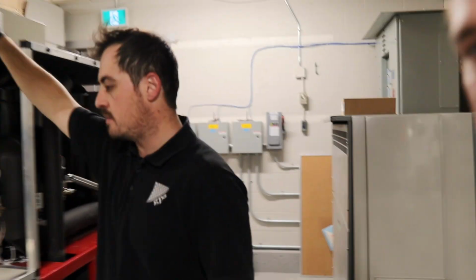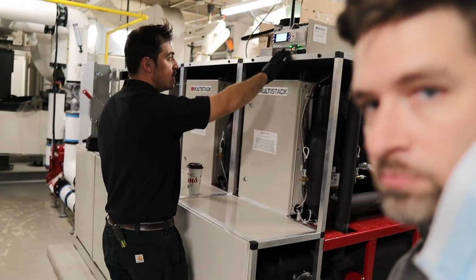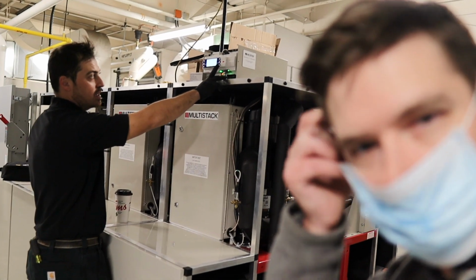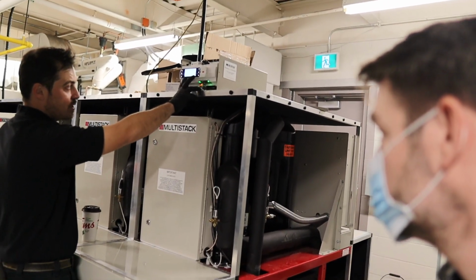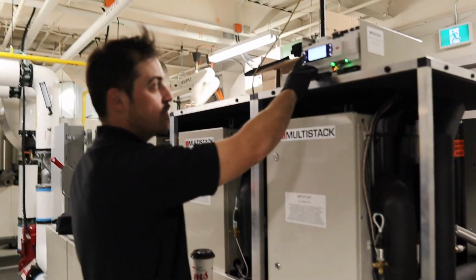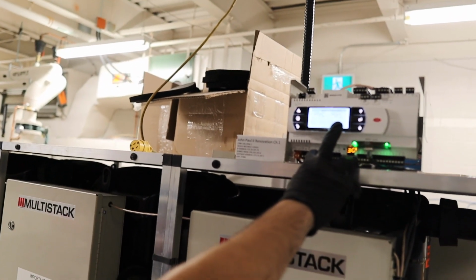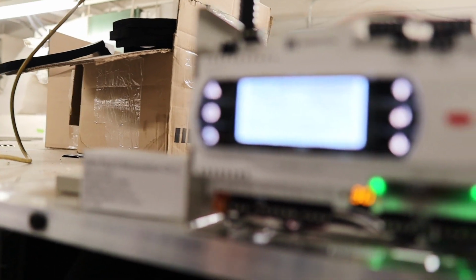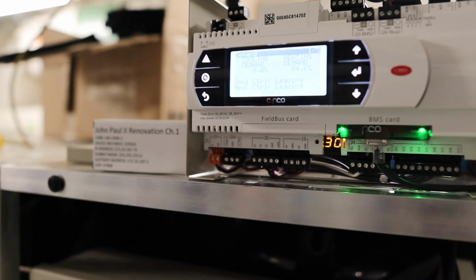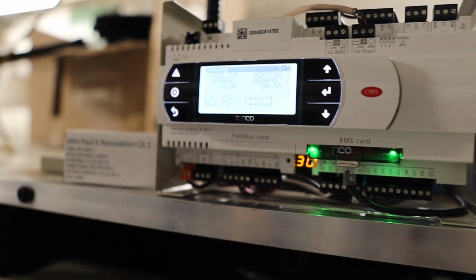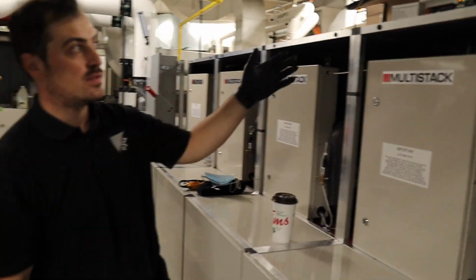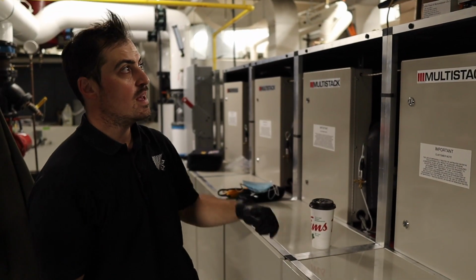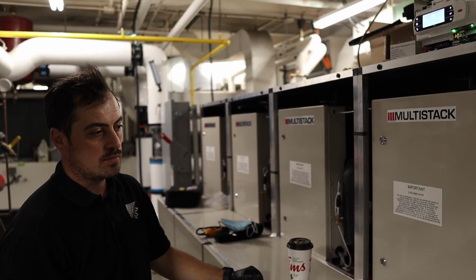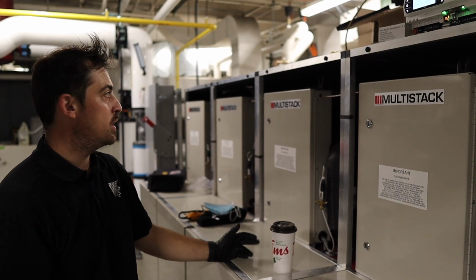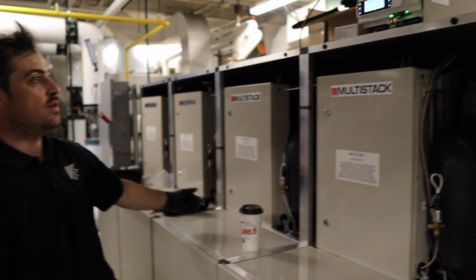Yeah, once we have our design parameters, we log that information into our microprocessor, and it monitors the water coming in and out on both the condenser side and evaporator side, and it decides how much percentage. For example, over here you have 84 demand for heating and nothing for cooling. That could be because there's no demand, or there are no pumps on right now. Once there is a demand, then we can start transferring energy from one area to another. There has to be enough energy to be transferred from the cooling side to the heating side to be running. So in our case, it's 25% minimum.